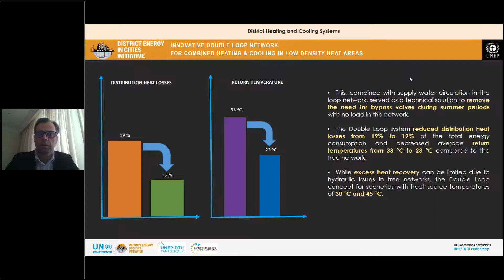The double loop network reduced distribution heat losses from 19% to 12% of total energy consumption, which is also quite a good result. Also, return temperature decreased from 33 to 23 degrees compared to the tree network. While excess heat recovery can be limited due to hydraulic issues in tree networks, and we know these issues and problems when we have excess heat but still have a tree type network, the double loop concept for scenarios like this, with heat source temperatures of 30 or 45 degrees, can help to solve these issues.